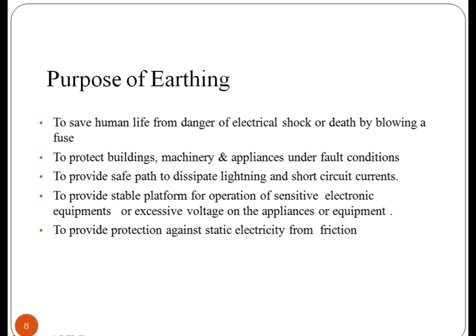Why is earthing performed? The main purpose of earthing is to save human life from the danger of electrical shock or death by blowing a fuse, that is, to provide an alternative path for a fault current to flow so that it will not endanger the user. To protect buildings, machinery and appliances under fault conditions, that is, to ensure that all exposed conductive parts do not reach a dangerous potential. To provide a safe path to dissipate lightning and short circuit currents. To provide a stable platform for operation of sensitive electronic equipment, that is, to maintain the voltage at any part of an electrical system at a known value so as to prevent overcurrent or excessive voltage on the appliances or equipment.